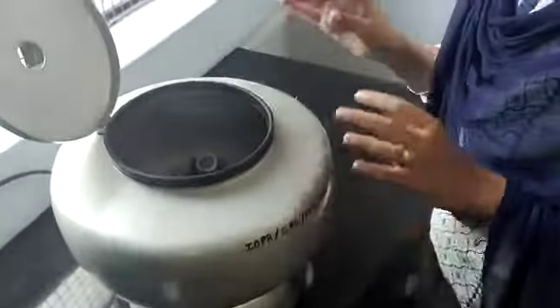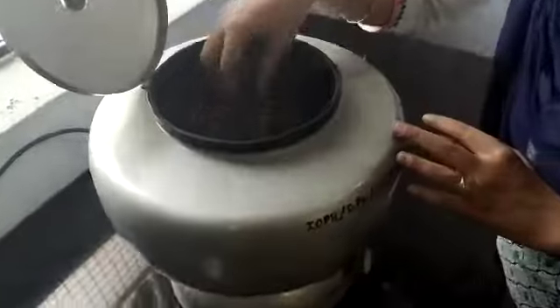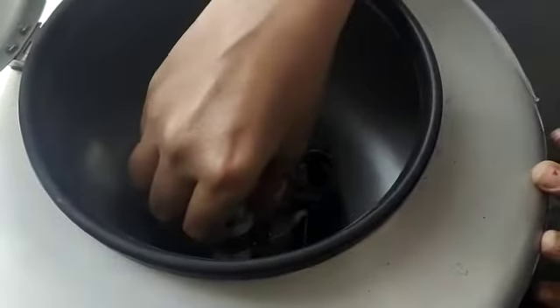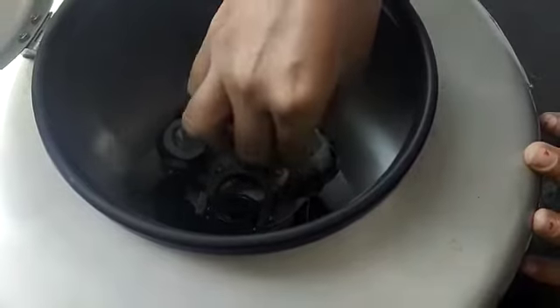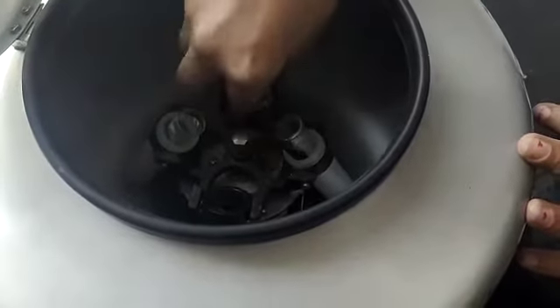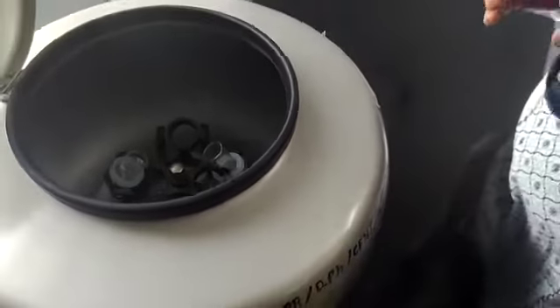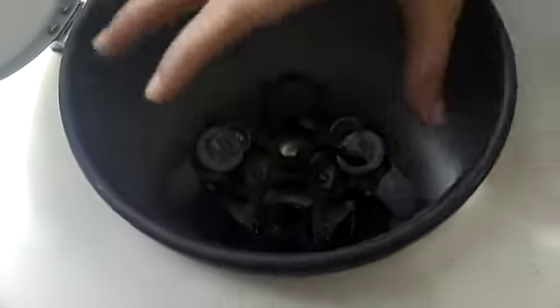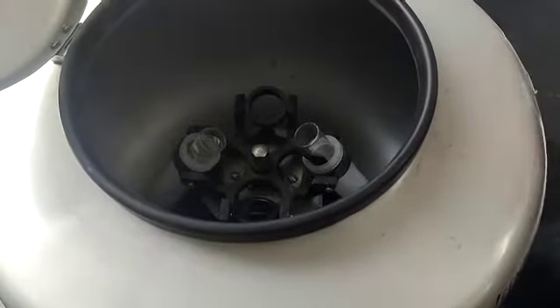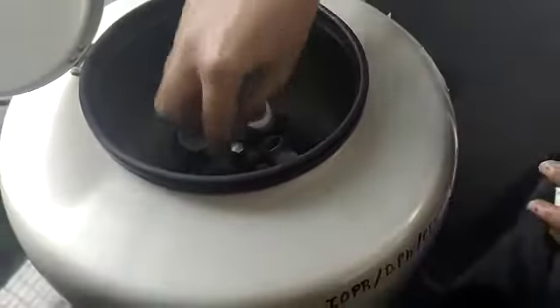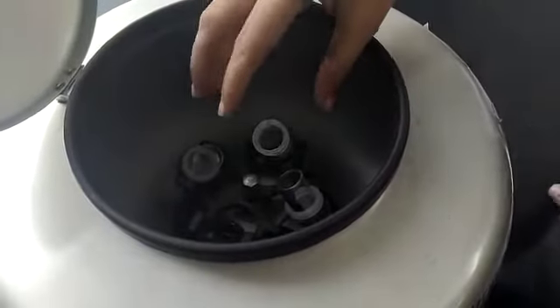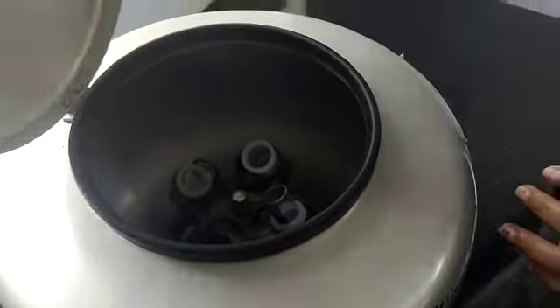While operating, we have to keep in mind that we must always balance the centrifuge tubes in the rotor. So even if you are running one sample, you have to keep other centrifuge tubes, you may fill them with water, or you may keep two centrifuge tubes in opposite directions so that it is balanced symmetrically. Otherwise a destructive vibration may occur. So it is always recommended to load all the buckets into the rotor. So this is all about the centrifuge chamber.